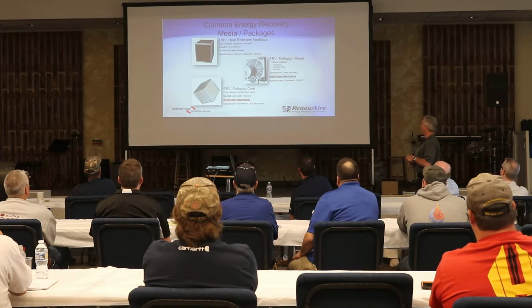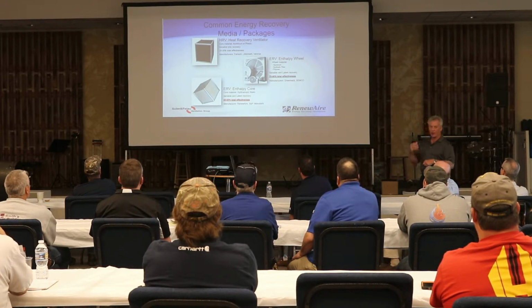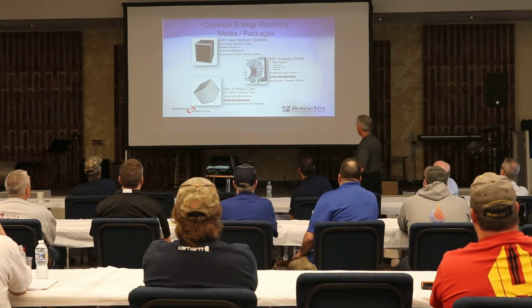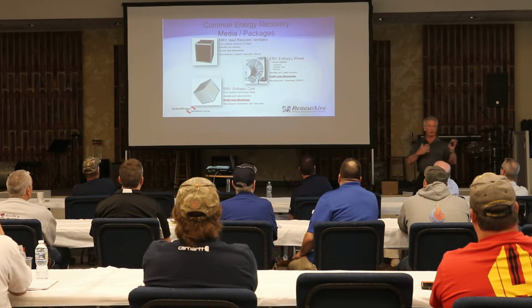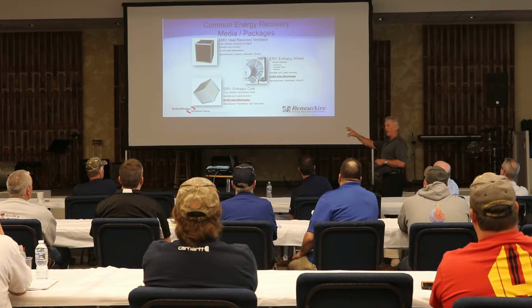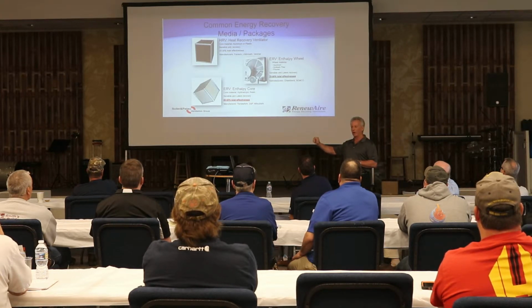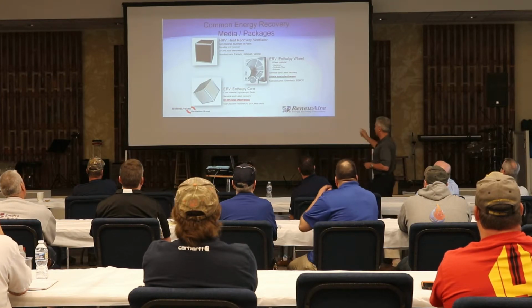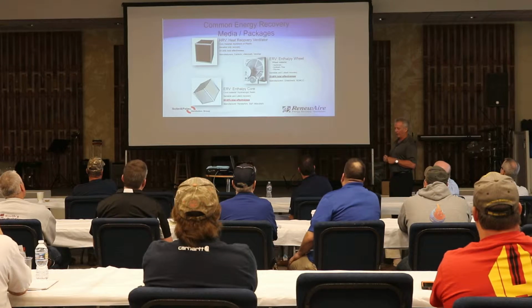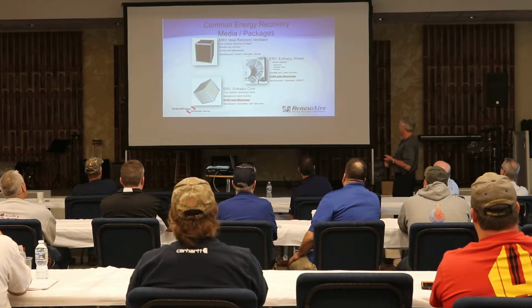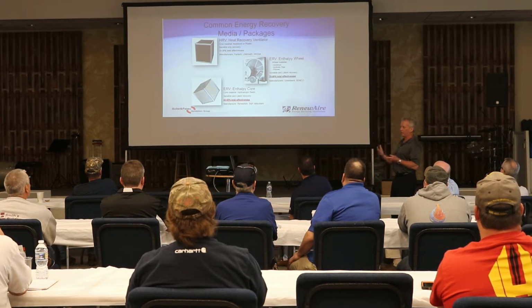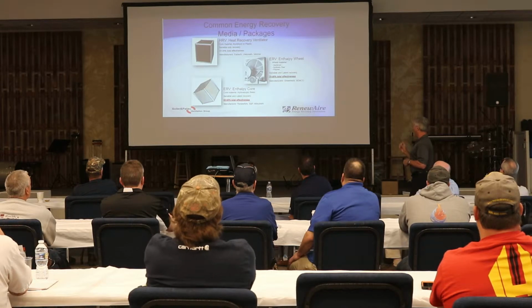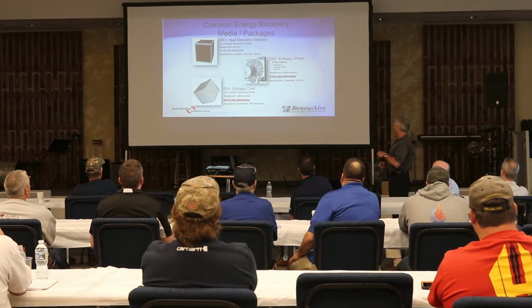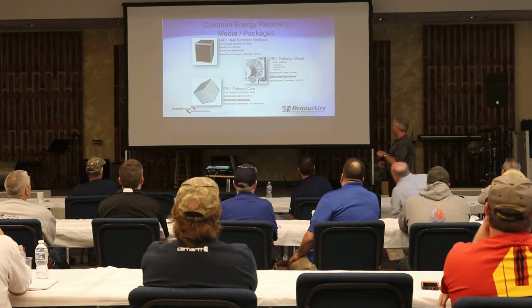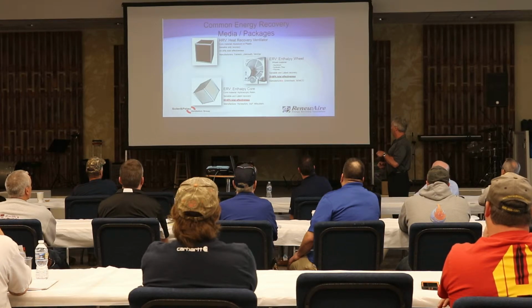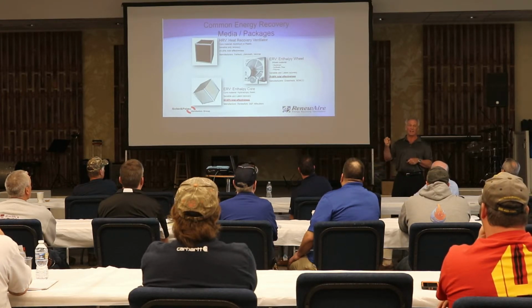The total effectiveness is going to be limited to about 20 to 30%. There are a lot of manufacturers of the finished devices as well as core materials. Just to present a complete picture here, in the ERV, or energy recovery ventilator, category, there are basically two different options. One is an ERV wheel or an enthalpy wheel that will do a sensible and latent exchange, and those wheels will come in a number of different materials. Aluminum, synthetic fiber, or a polymer would be the typical way these things are transferring both sensible and latent heat. Very good total effectiveness. These are typically seen in commercial applications.